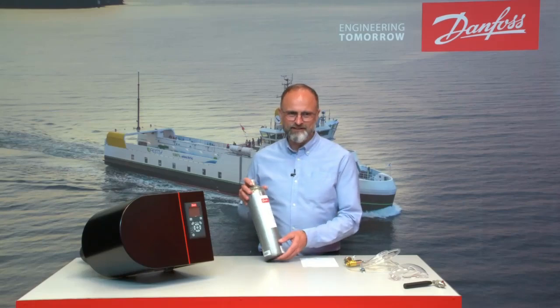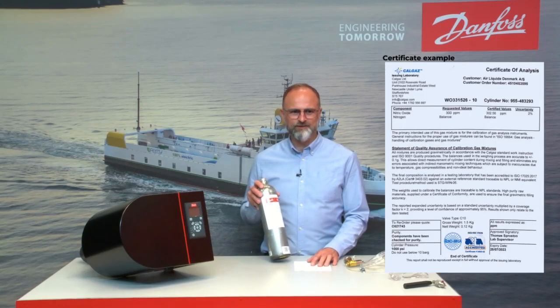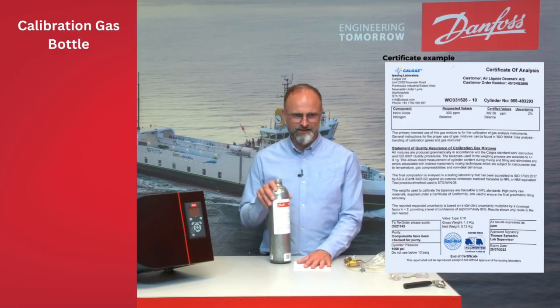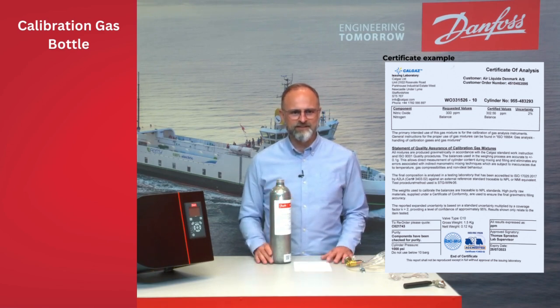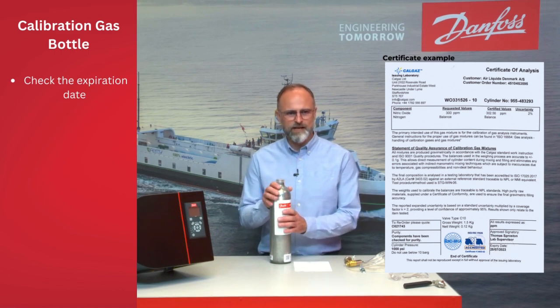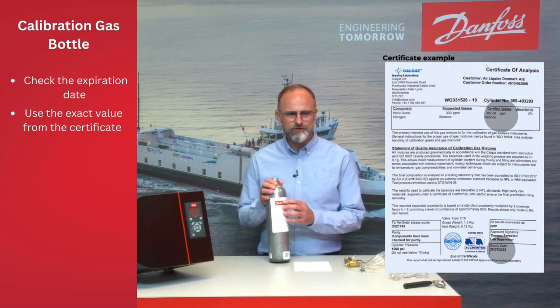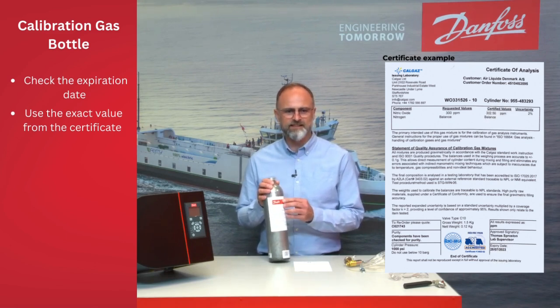The span gas bottle comes together with a certificate that you need to be very careful about. It contains an expiring date that you need to check is still valid. It has the value of the span gas. The standard value is 300 ppm, but the actual value of the gas inside the bottle is a little bit different. And for the calibration, you need to use this exact value.